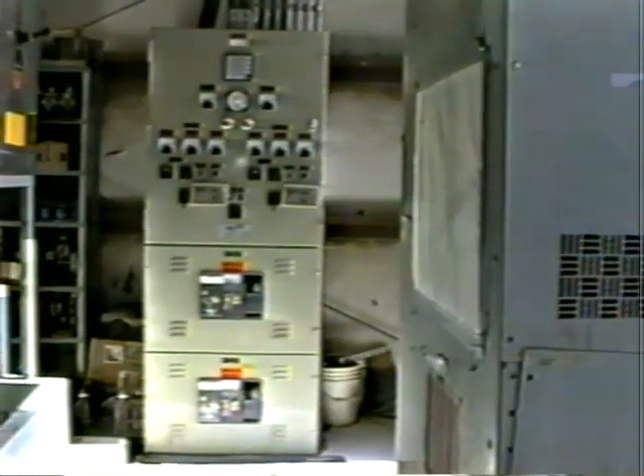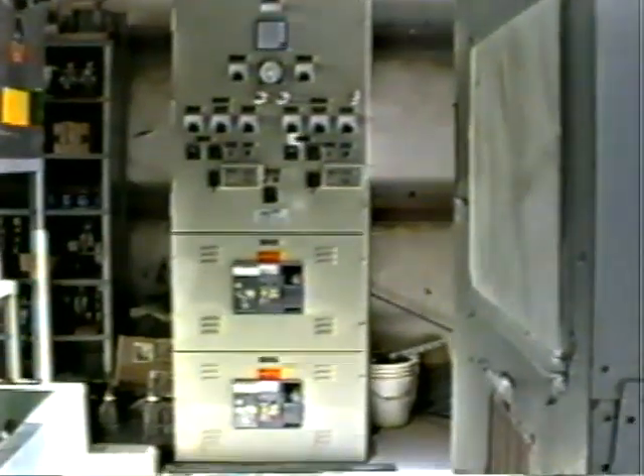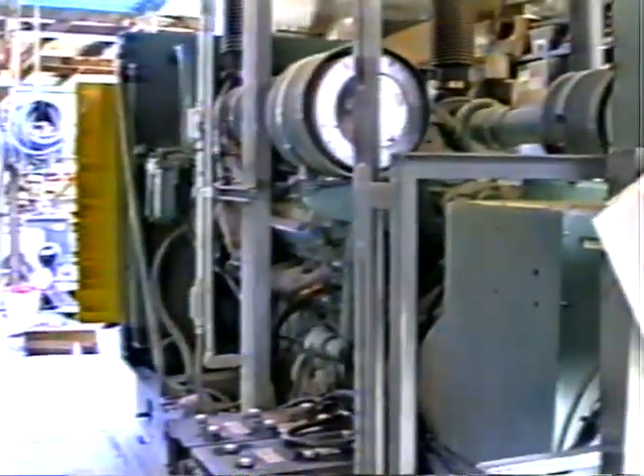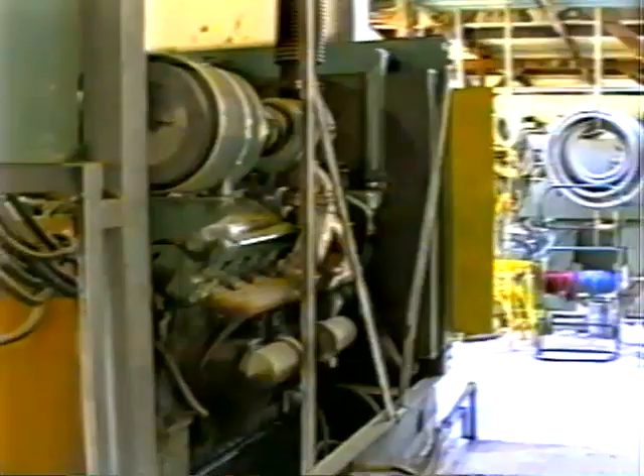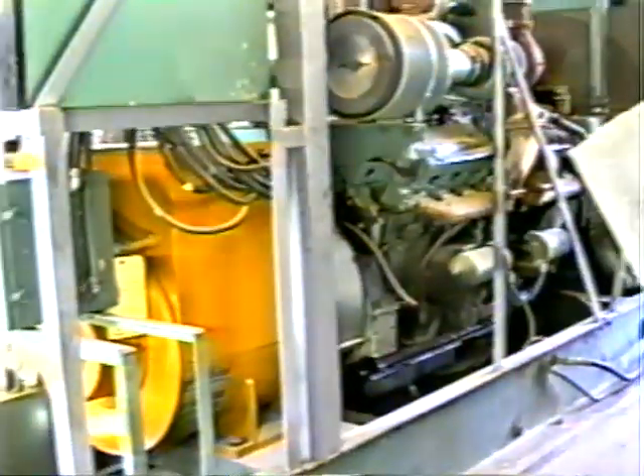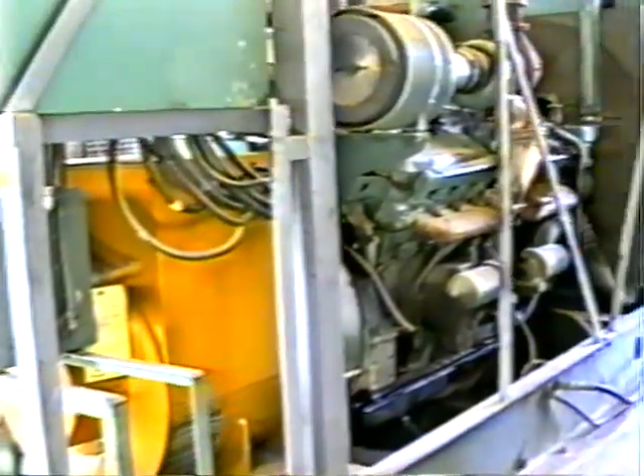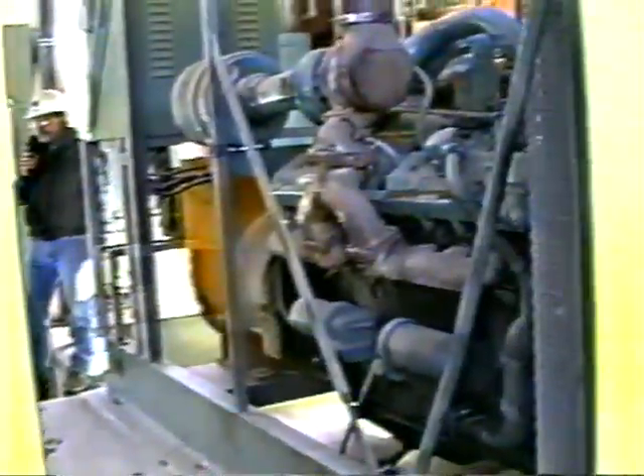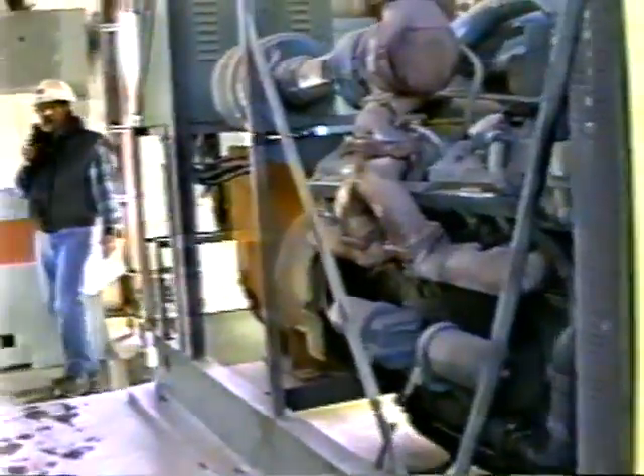We're now in the emergency generator room, where we have backup power supply if we have a power outage. We have 2 Detroit generators, 500 kW each, and they allow us to power up all the critical items if there is an outage. For example, our concentrate thickener, our tailings thickener, our tailings booster pumps, and various pieces of critical equipment in the concentrator itself. These units automatically kick on if the power is interrupted. They equalize themselves and allow us to, from the control room, start all the equipment that we need to start. And they have been, again, very reliable.